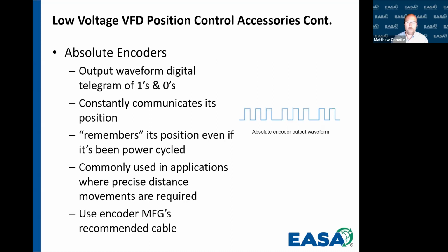One of the newer types of encoders, and one that I really like, is called an absolute encoder. An absolute encoder is used for positioning, and you can actually use it for speed control as well. Its output waveform is different. It's a digital telegram. It's made up of ones and zeros. It could be in binary or hexadecimal or some other form. And it's constantly communicating its position.